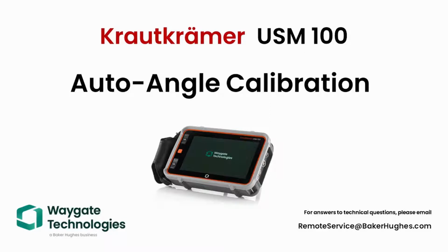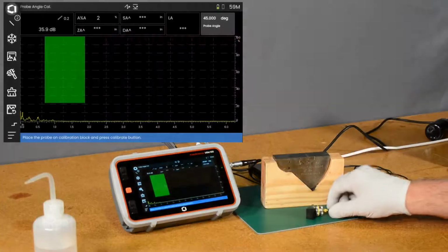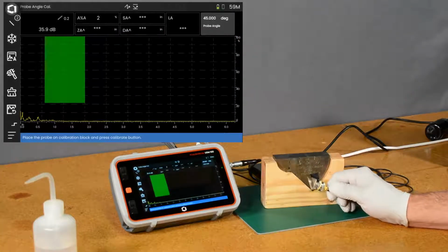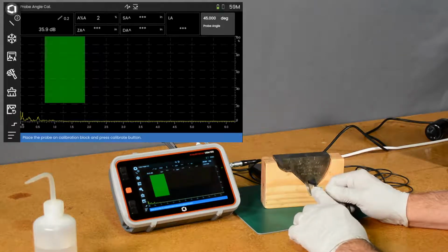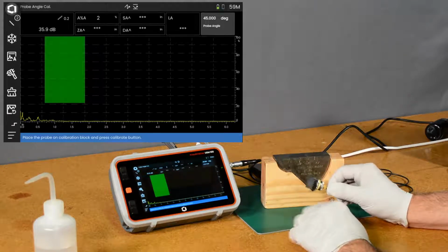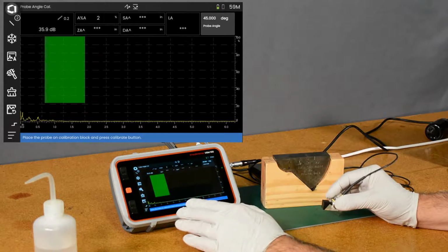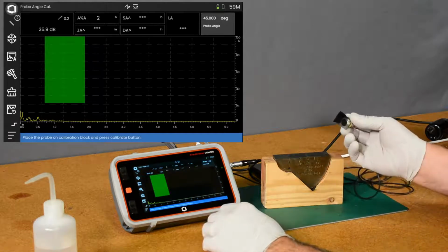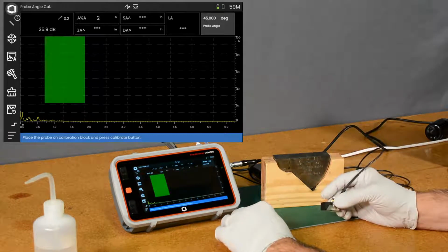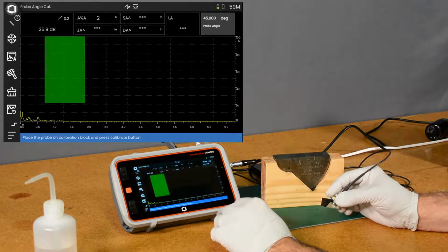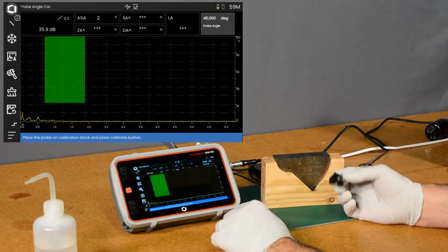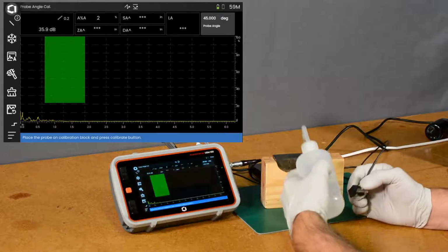the USM 100. This time we're going to be taking a look at the auto angle calibration. So it's a good way to check the angle of a wedge for a shear wave inspection. I've already gone through and set up the probe delay and material velocity using our 2-point calibration. And now we'd like to check the angle of the wedge.